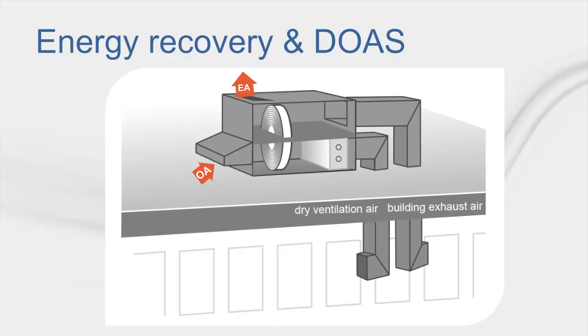Now that we've covered how to configure DOAS in TRACE, the DOAS unit may include an energy recovery device such as a total energy wheel that conditions outdoor air prior to entering the coils. The wheel preconditions the outdoor air by exchanging both sensible and latent heat with the exhaust air. In heating mode, the wheel warms and humidifies the outdoor air; during cooling mode, the wheel cools and dehumidifies the outdoor air.